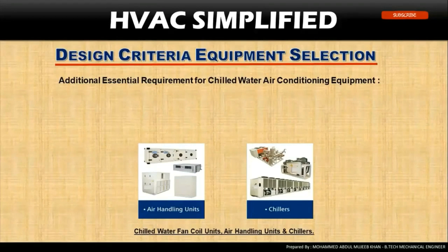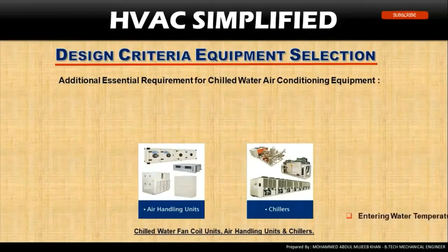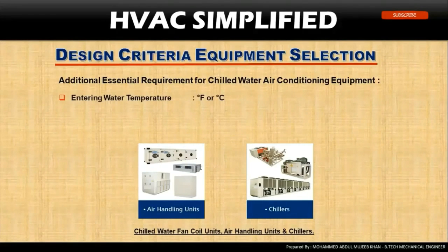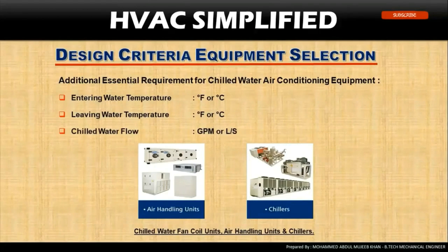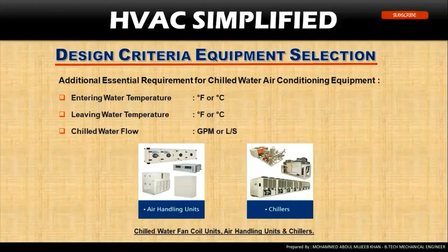For any chilled water system, these are the important additional essential requirements along with the previous ones: entering water temperature, leaving water temperature, and chilled water flow rate. You need to consider these three important factors when selecting any water-cooled chiller, water-cooled air handling unit, or chilled water fan coil unit.